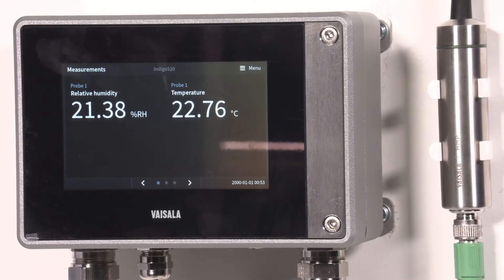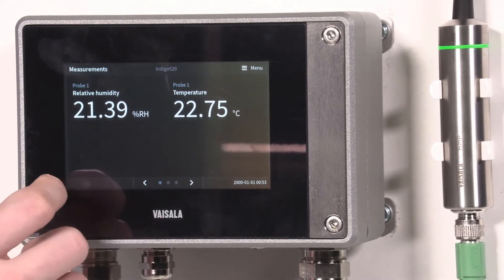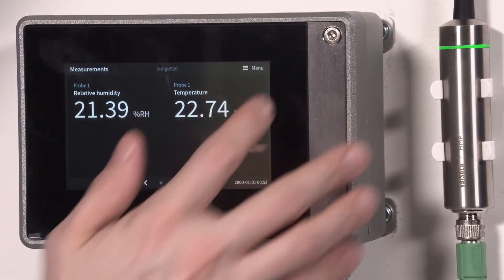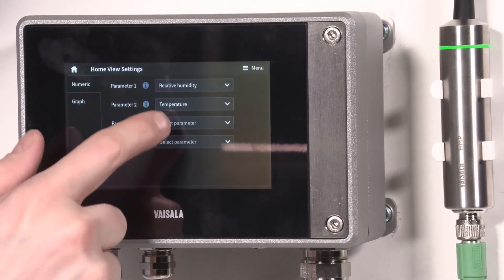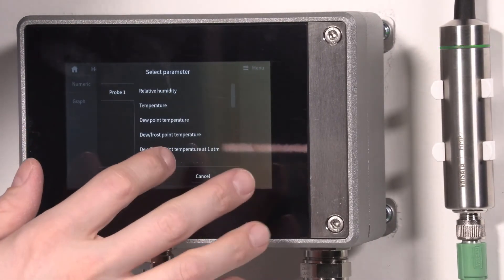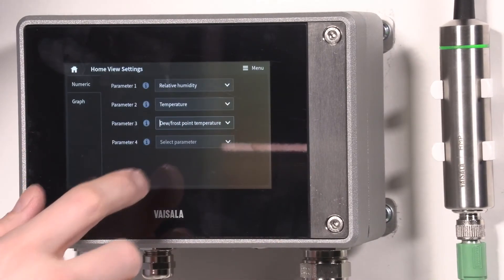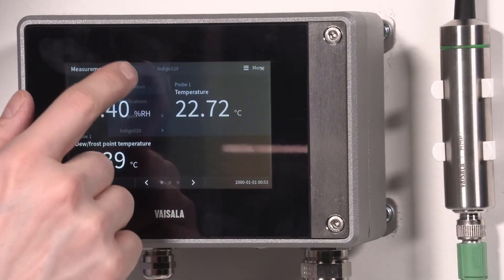The final thing is to configure this software so that it's similar to the 330 series. In the display, we had three different values: relative humidity, temperature, and dew point temperature. That's the first thing we want to add here. Home, views, and parameter three we select dew point temperature, and here we have the dew point temperature value also.